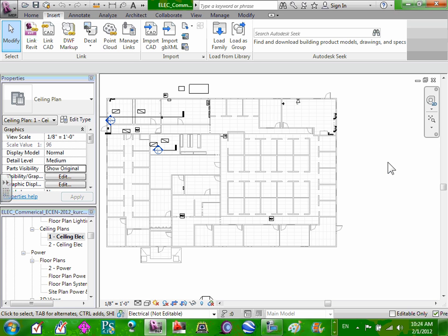And with 2x4 light fixtures, a 4-foot lamp versus a 2-foot lamp usually has a little bit more output and a longer lamp life. So we try to stick with the 2x4 fixtures. I would imagine the 2x2 is more expensive, a new shape. Yep, less common means more expensive.